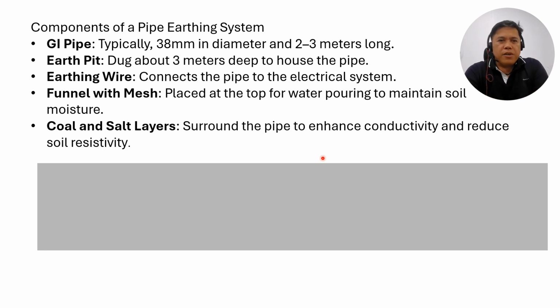Coal and salt layer surrounds the pipe to enhance conductivity and reduce soil resistivity. Sometimes, if you are an inspector, you do the continuity test of the earthing, and sometimes the low resistance value doesn't reach the requirement. That's why all these components need to be achieved.